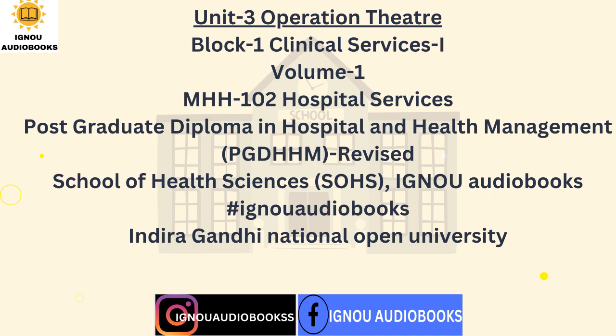The services include providing medical gases like oxygen, nitrous oxide, compressed air and suction through the centralized pipeline system to the wards, operation theaters and ICU etc. These gases are supplied from the manifold plant, round the clock. In every shift, there is a technician, plant operator, to maintain proper and regular supply of the above said gases.